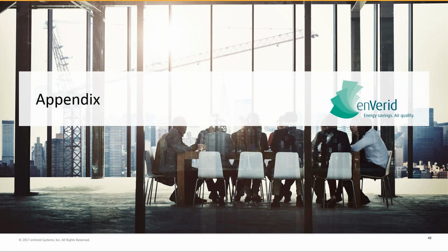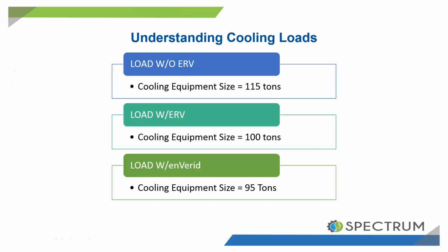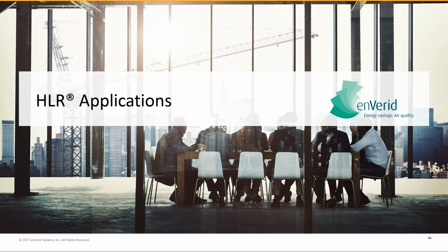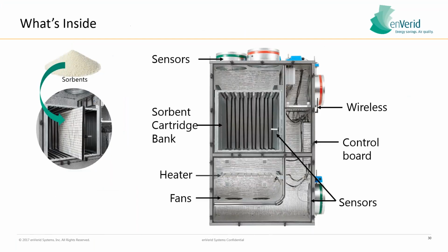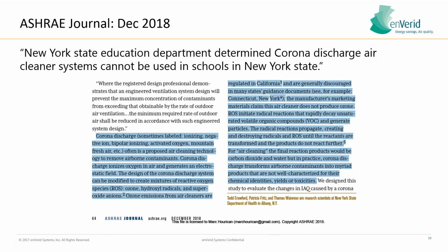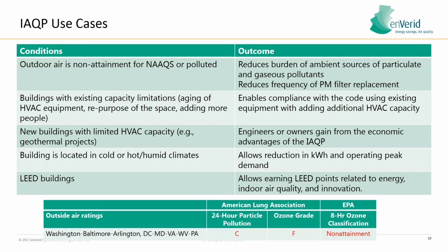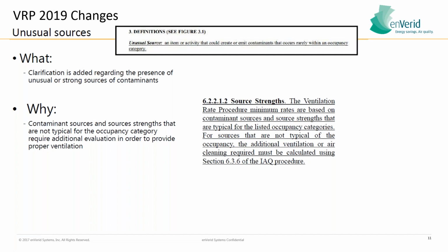That being said, if outside air quality is questionable, you are supposed to use the indoor air quality procedure. So if you're in your mind right now saying, what's an unusual source or how close is too close? According to this statement by ASHRAE, you're supposed to use the indoor air quality procedure. And I'll just pull up that verbiage once again for everybody so you can look at it. Don't get dizzy. And there it is. For sources that are not typical of occupancy, the additional ventilation or air cleaning required must be calculated using the indoor air quality procedure.